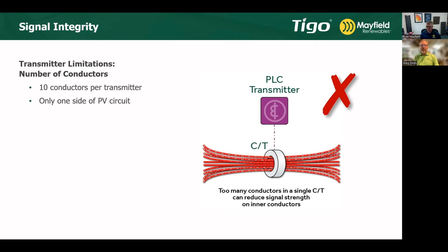We just had this issue, like 3 or 4 weeks ago. The guy jammed like 15 or 16 conductors in, and the ones in the middle weren't getting signal - it was a signal integrity issue, not crosstalk. We just added another core, split the conductors up, good to go. That's a good point, because crosstalk was kind of the focus of this presentation, but we've moved into signal integrity. This by itself is not a crosstalk issue, but they're adjacent, because you've got to maintain that signal in order to get to your MLPEs out there.